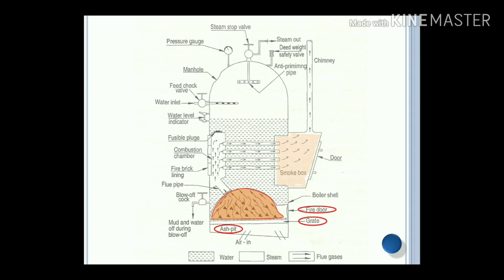Smoke box: after generating the hot gases, they pass through the fire brick lining and inside the tubes, and heat exchange takes place from inside the tubes to the surrounding water. With the heat exchange, water is heated up to a certain limit and it will produce high-pressure, high-temperature steam. With the help of the smoke box, waste gas is collected and directed towards the chimney.